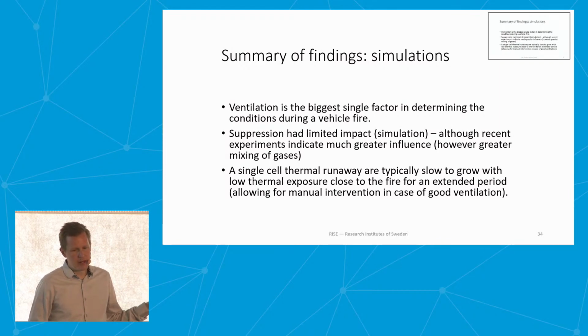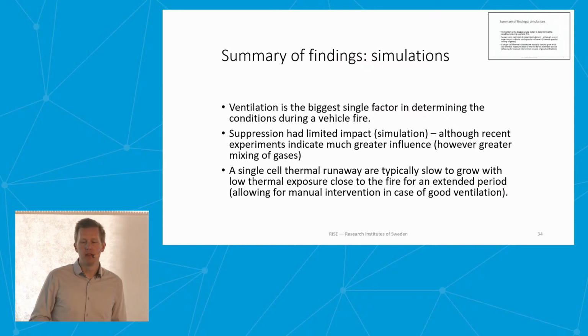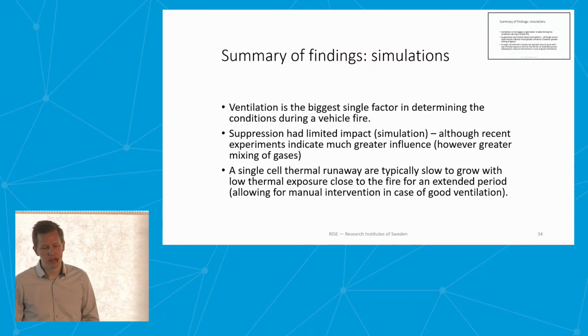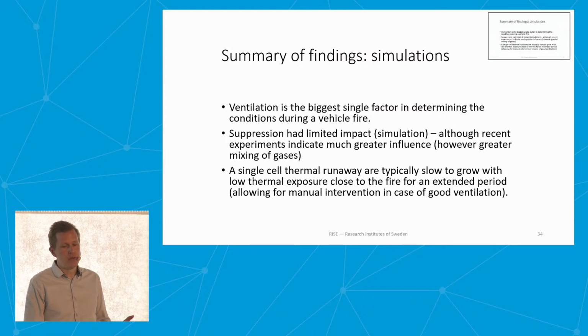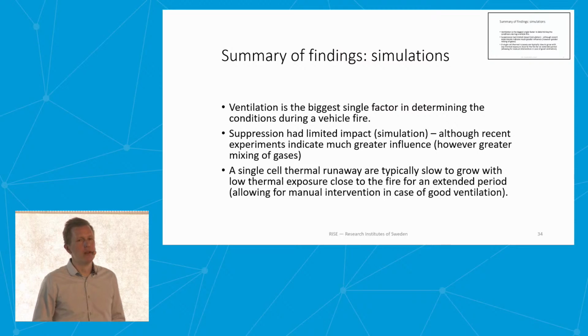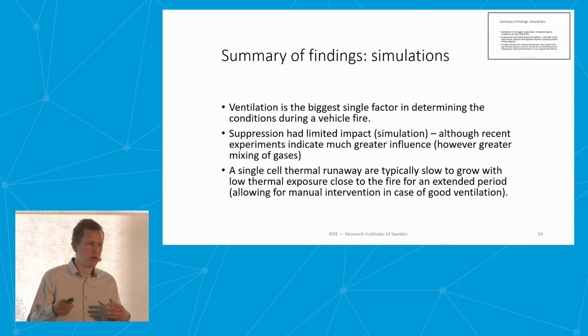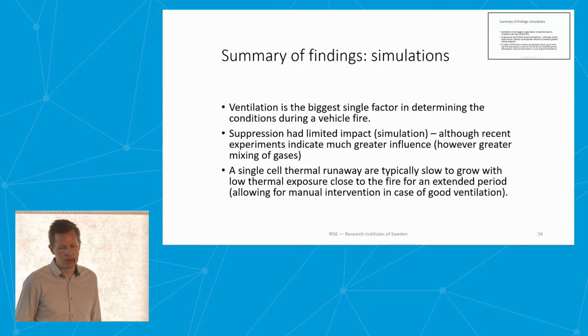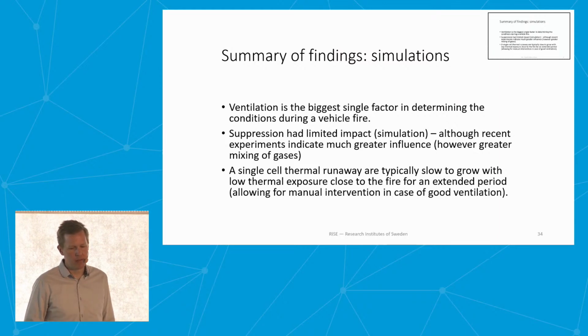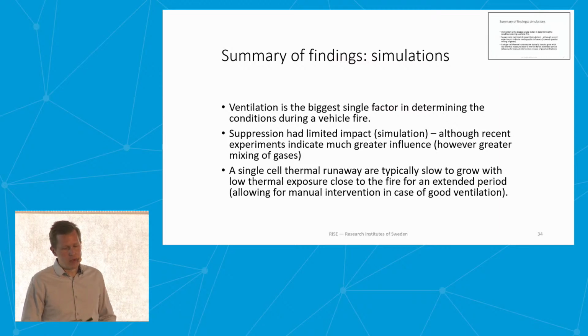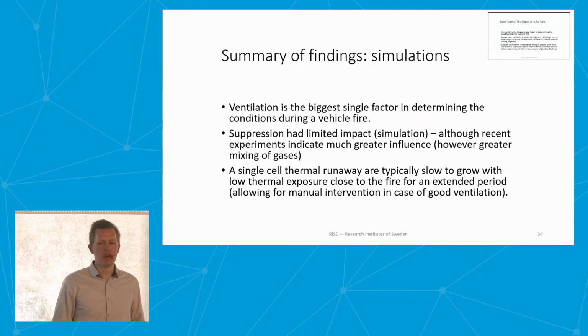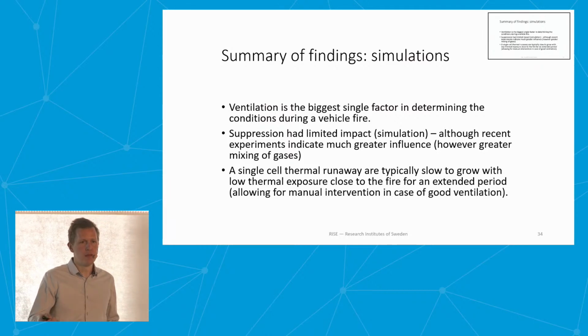In the simulation, suppression had a limited impact, but that's because it's quite hard to simulate. From testing, we see that suppression actually has a good effect, also in terms of toxicity. However, it will cause greater mixing of gases, which could make things worse with regard to visibility if you're doing manual firefighting at the same time. Also, the thermal runaway scenario is quite slow compared to a large fuel spill fire, and for a long time, as long as you stay out of smoke and jet flame, you can be quite close to this kind of fire.